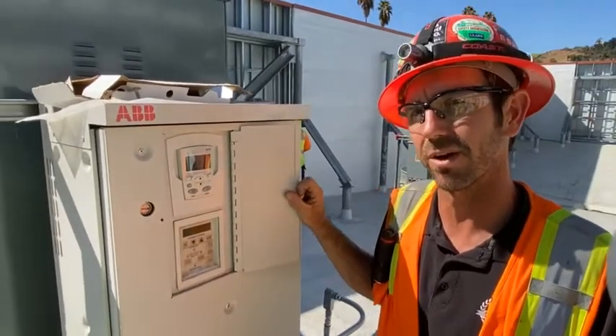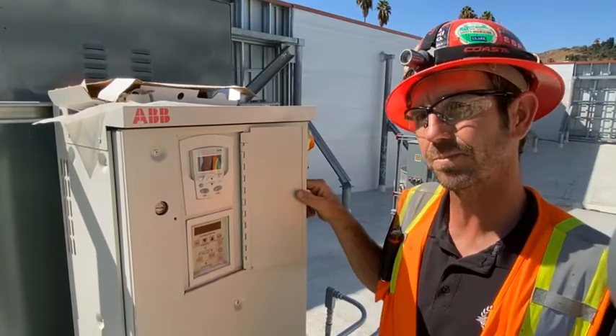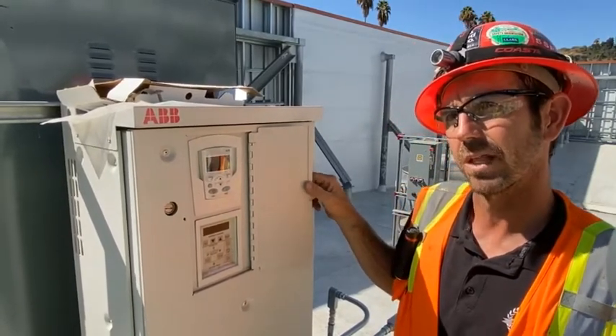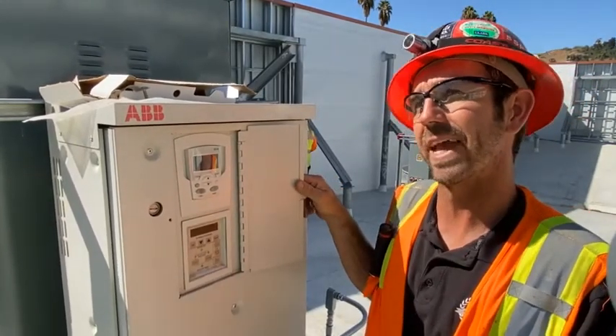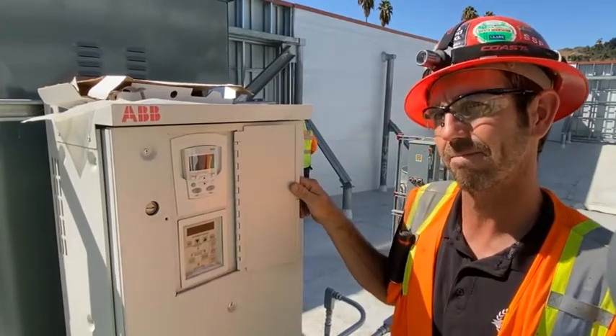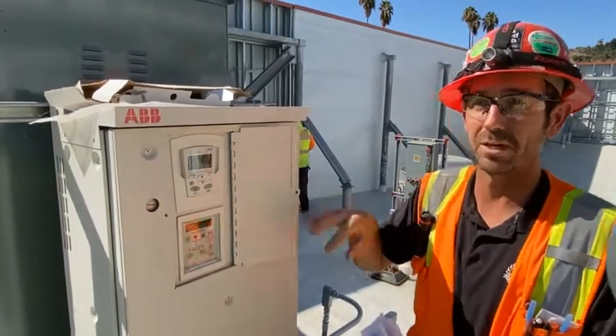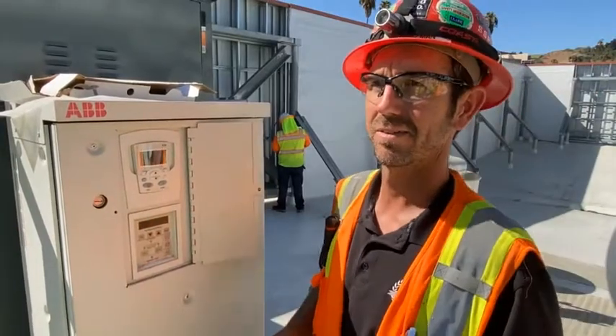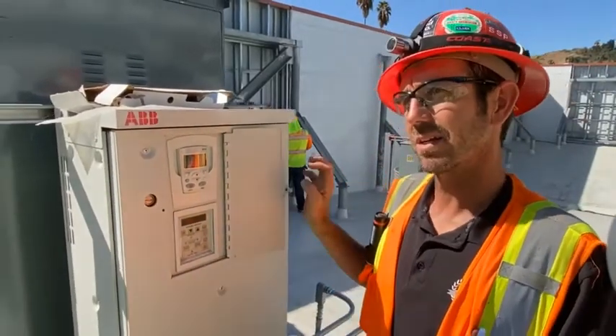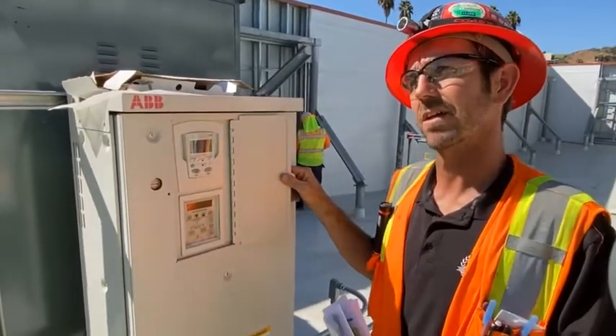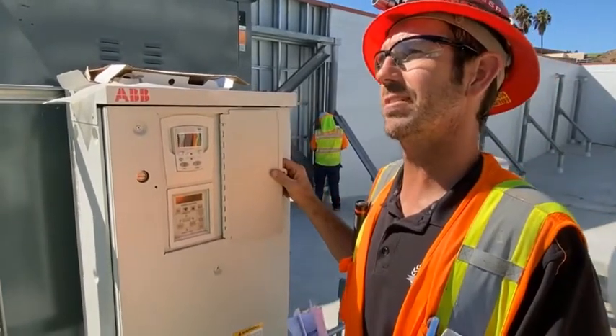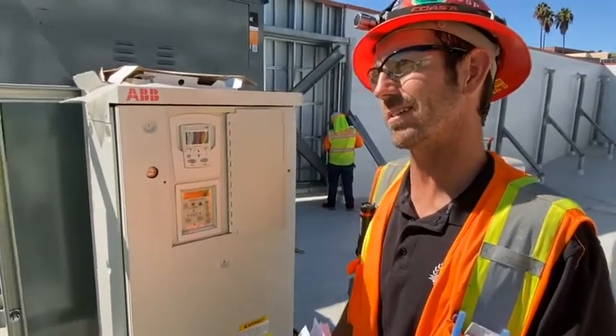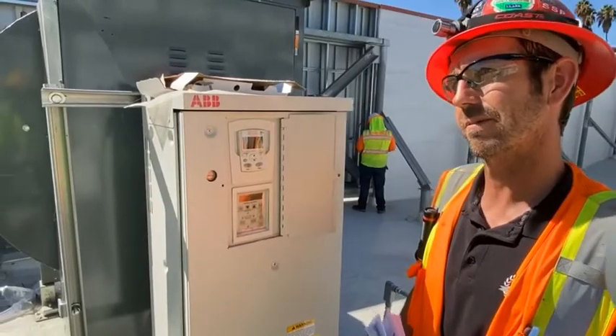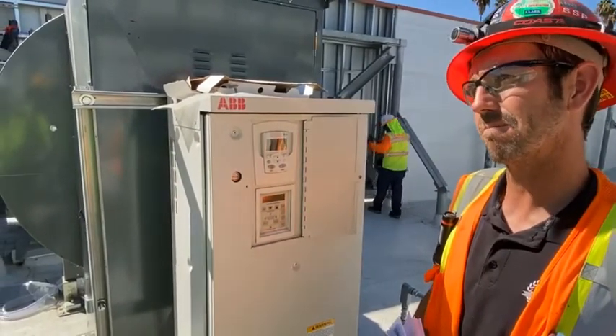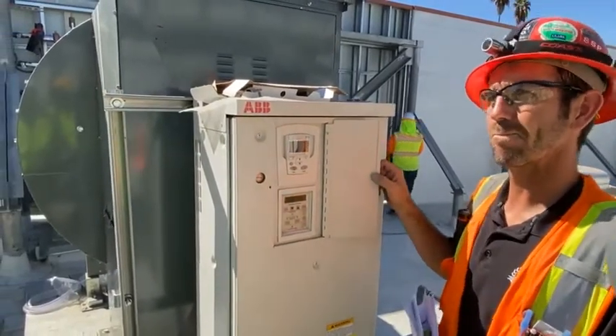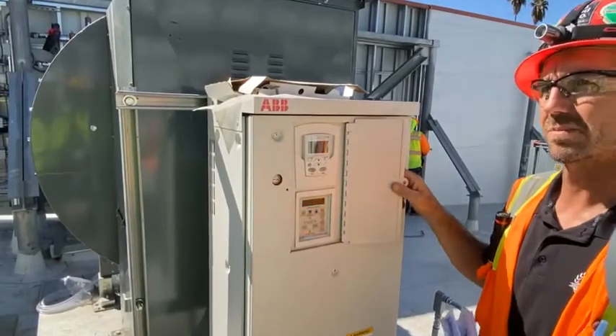Is this tied in with the HVAC controller so we can see it on the computer? Like I said, the only thing you'd see here is status that the fan is running. But as far as turning it on and off through the BMS, no. I just wondered if there was anything that would say it's got pressure in there, so we could verify that it's running. Just a status current sensing donut is the only thing I was aware of. So it's a sensor. Yeah, if we get current flowing through it, it'll say that it's on or off. It's not a contact switch.